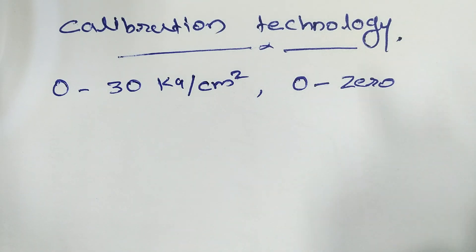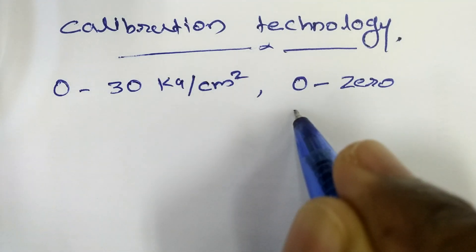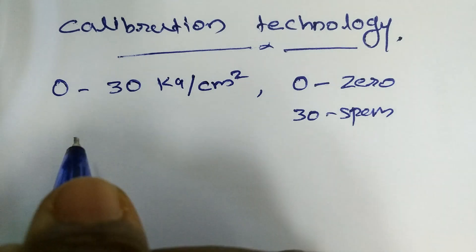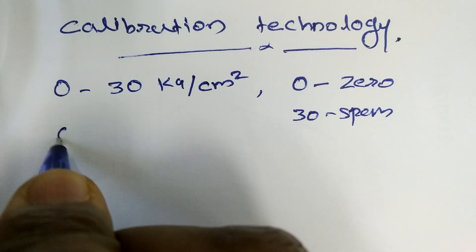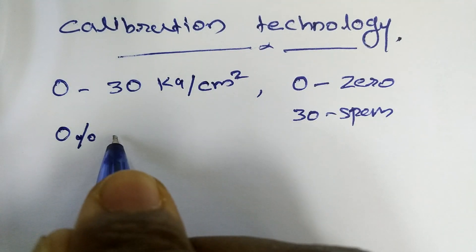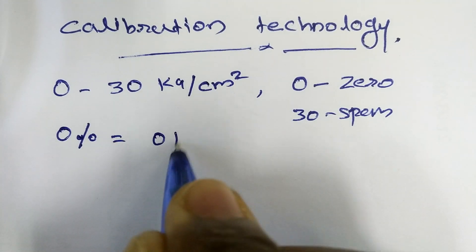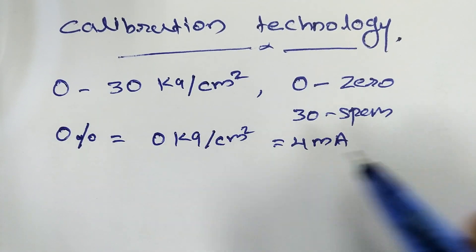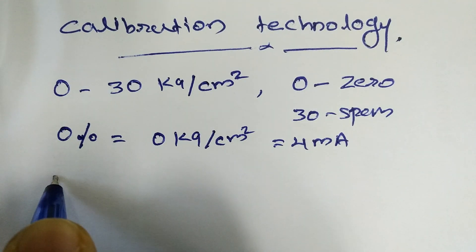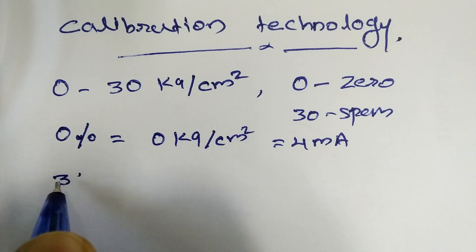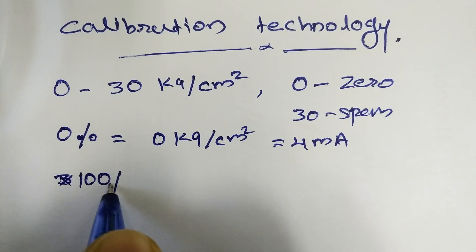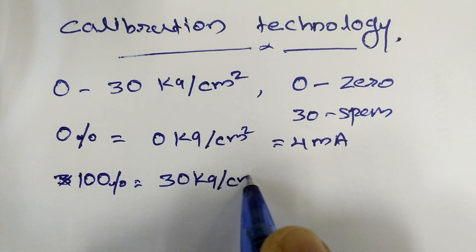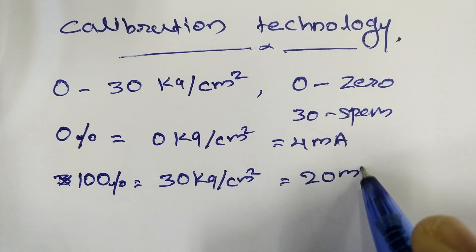Now, the range of this transmitter: 0% is equal to 0 kg per centimeter square, which is equal to 4 mA. And 100% is equal to 30 kg/cm² which is equal to 20 mA.